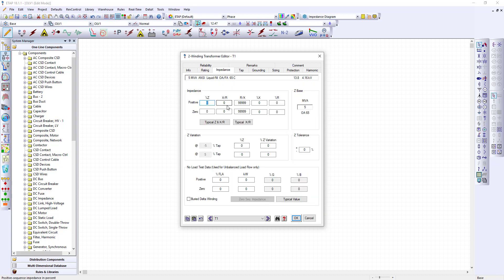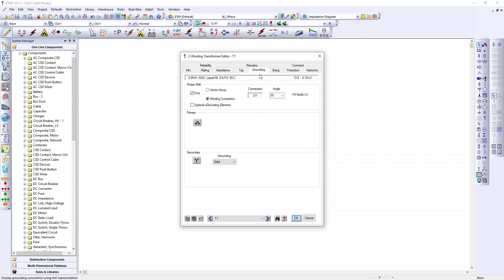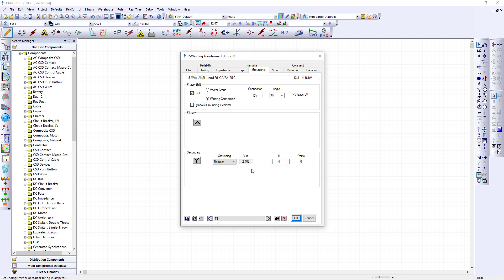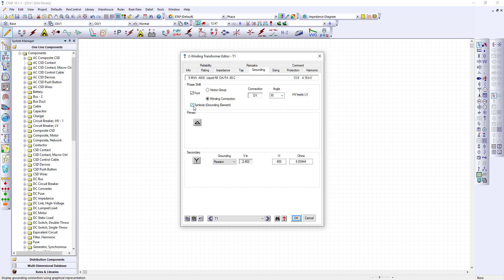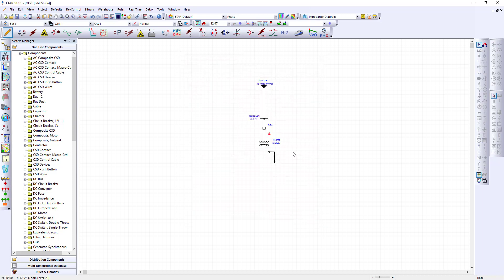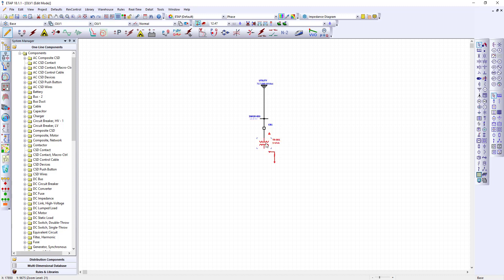Impedance we will put typical values. If you have nameplate data you may use nameplate data. Also grounding. The grounding in this transformer is resistance grounded and we're going to put in 400 amps. It will automatically calculate the ohms. I like to also do the symbols. Click the symbols box. Notice that you've got the symbols and you've got the transformer.